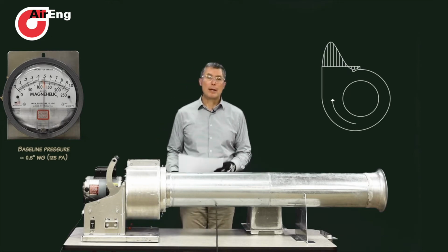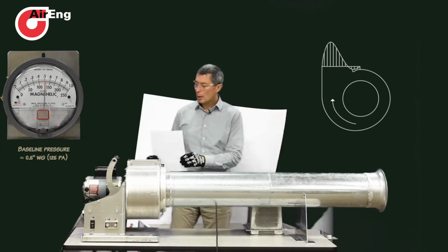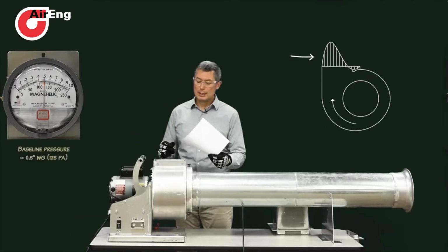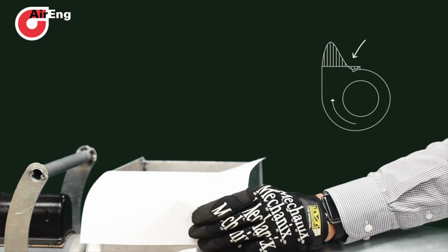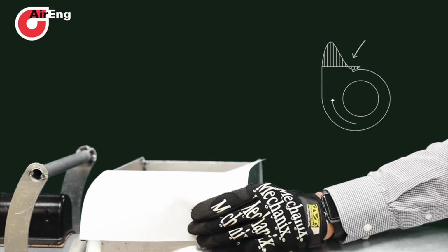And we can demonstrate that by using this piece of paper. Putting it on the outside of the volute shape, that piece of paper stands up vertically. Put it on the inside of the volute shape, it actually gets sucked into the fan just behind the cutoff sheet. There's a negative pressure region there.